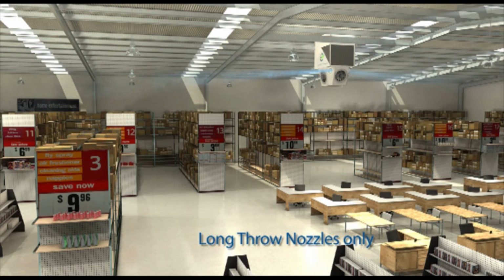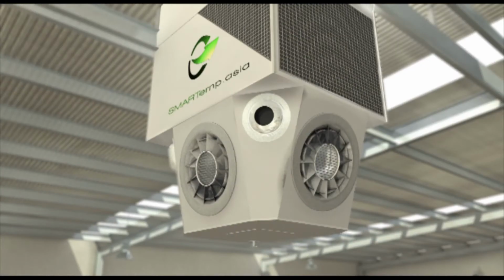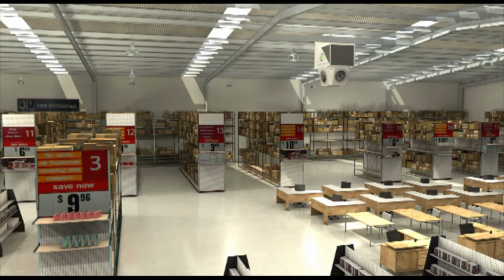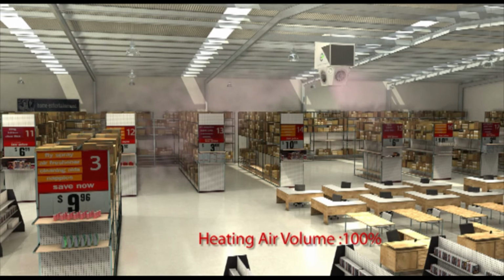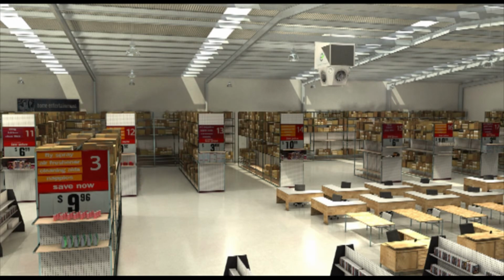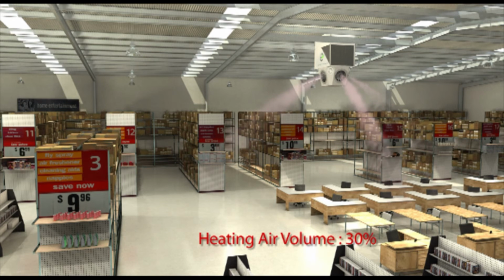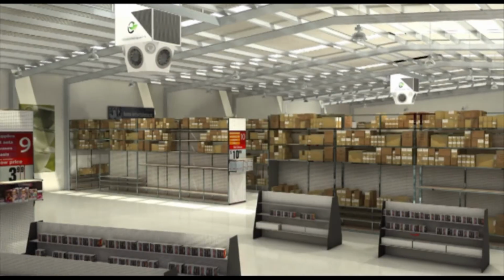Lights and signage will be unaffected by the airflow. The diffuser central core is motorized to swivel downwards when heating, and special control sequences are used to optimize the warm-up times of the space, which can be reduced by up to 10 times that of a conventional ducted system. Fresh air for the indoor air quality control is supplied into the occupied zone without stratifying. This reduces the amount of fresh air required, as CO2 sensors in the space adjust fresh air dampers accordingly. Substantial energy savings are achieved. The smart way to condition large spaces.